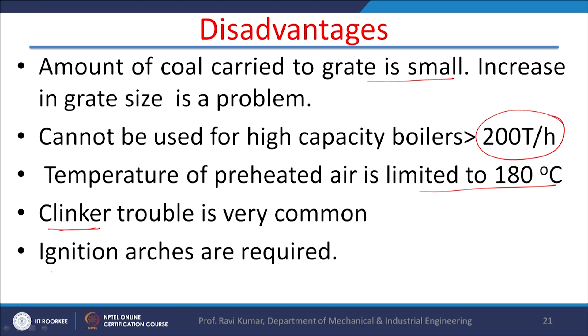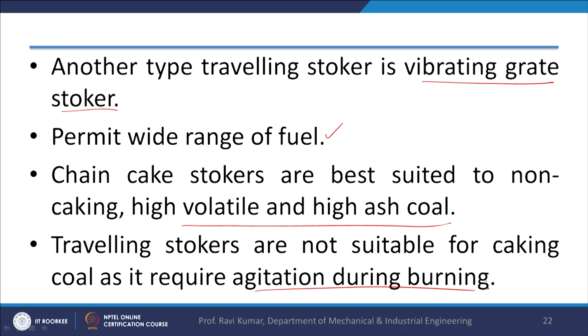Another is the vibrating grate stoker. Periodically the coal is fed through gravity by vibrating the beds. So, this is another method of feeding the coal. It permits a wide range of fuel. If the size of the coal is varying, then this type of arrangement can be used. Chain grate stokers are best used for non-caking, high volatile and high ash coal. Travelling grate stokers are not suitable for caking coal, as it requires agitation during burning. So, these are the limitations for this type of arrangement.